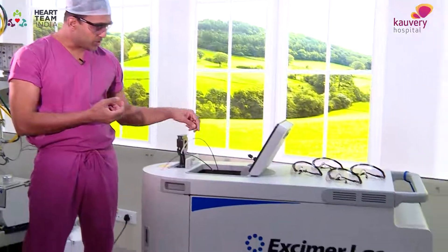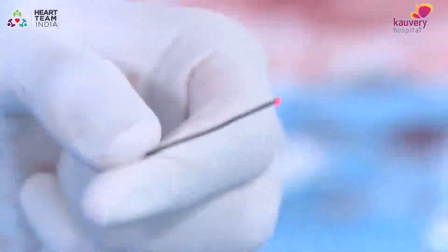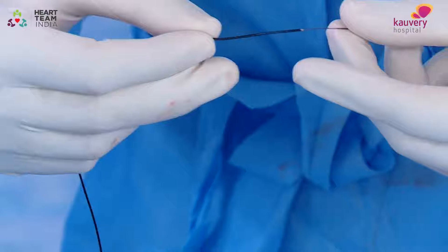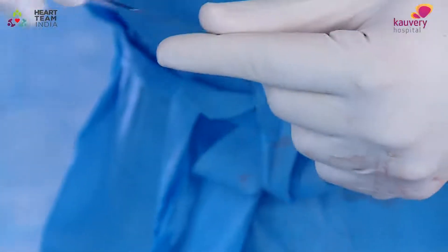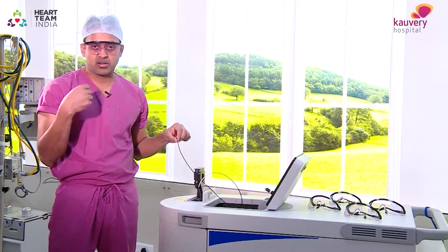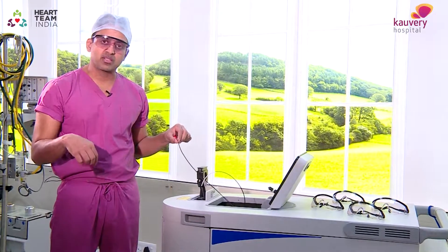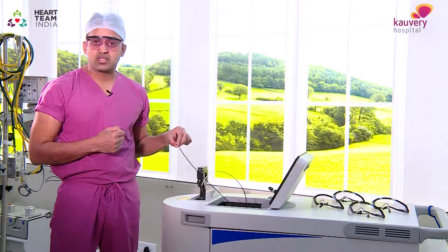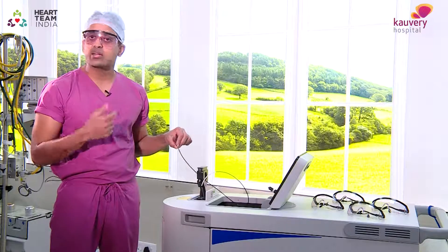This machine is the laser production console. It's a very large and heavy machine. From here the laser is produced and comes out of the tube, which is then connected to a fine catheter. It can be used for opening up blood vessels, angioplasty in the coronary tree. It can also be used for peripheral vessels or to extract intracardiac devices should there be an infection or a chronic lead problem.